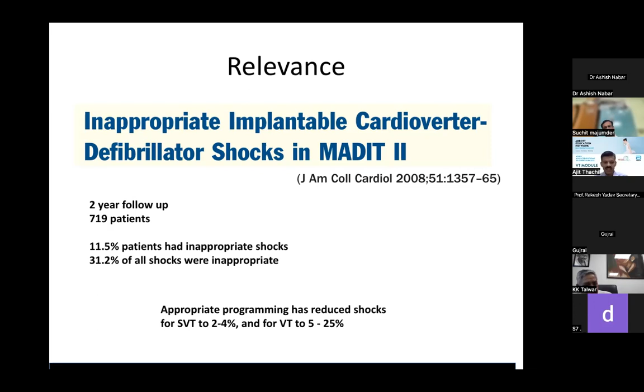So the relevance is this: 31% of all shocks in MADIT-II were inappropriate. Appropriate programming can reduce inappropriate shocks for SVT from 2 to 4%, and inappropriate shocks for VT, that is, VT which could have been terminated by ATP but got a shock, which is still called sort of inappropriate, to 5 to 25%.